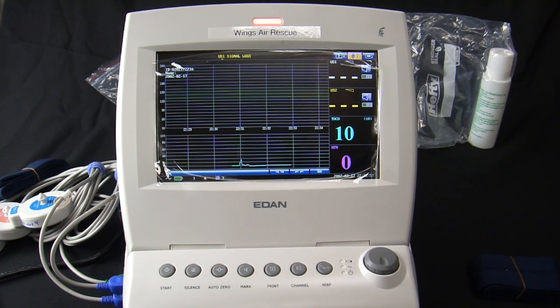Maintenance for the F6 should be done prior to use at any given time. Check the connectors and cables to make sure that none of them have been damaged or frayed. Look at the ultrasound and TOCO transducers to make sure that they are intact and have not been dropped or stepped on. The overall quality and safety check of the monitor should be performed every 6 to 12 months by a certified biomedical engineer to make sure that no damage has been taken by the machine.